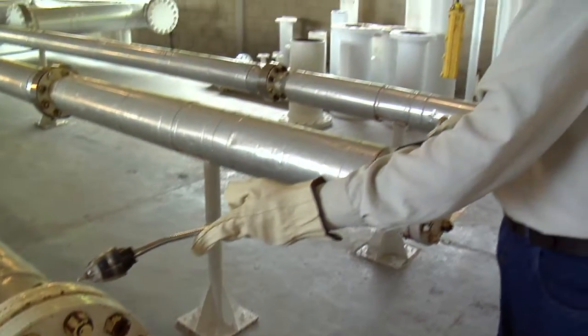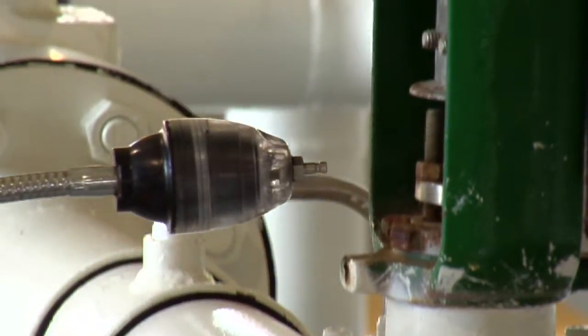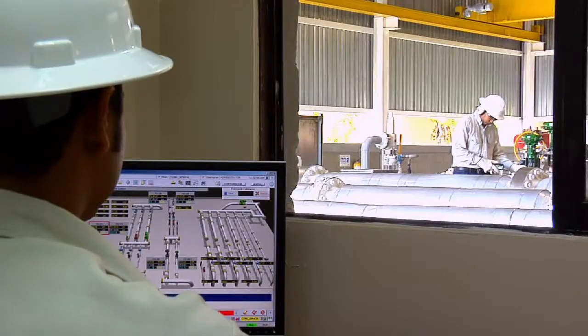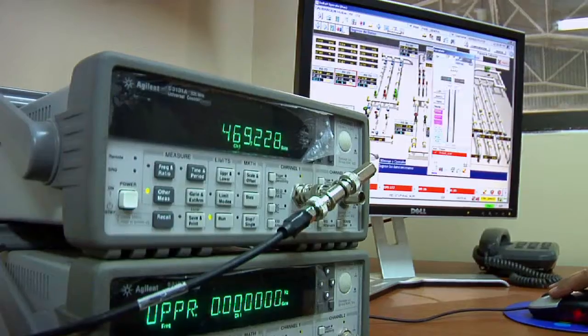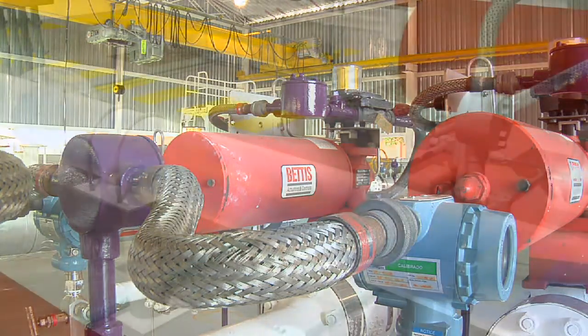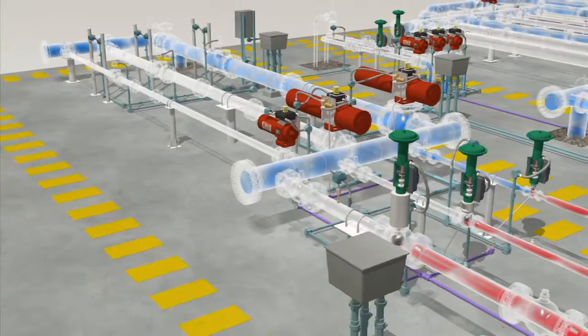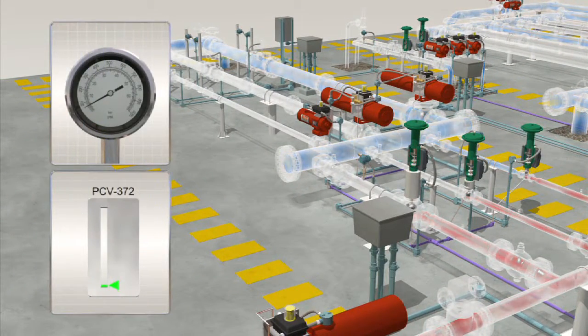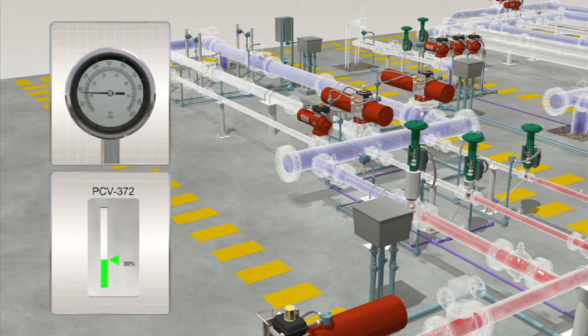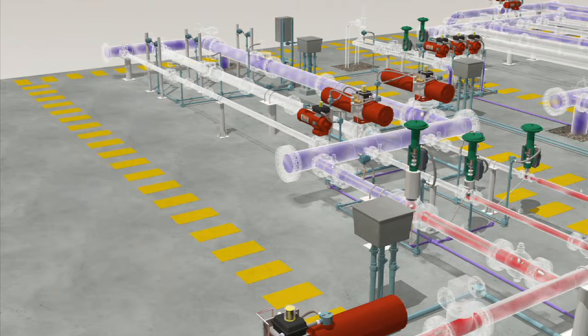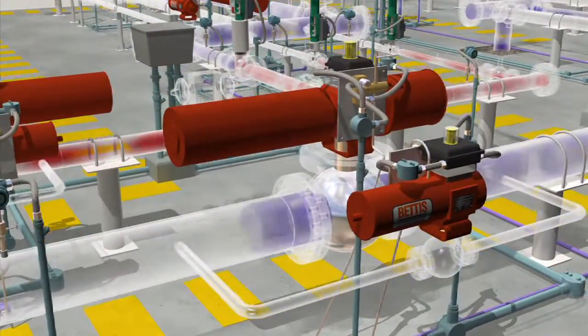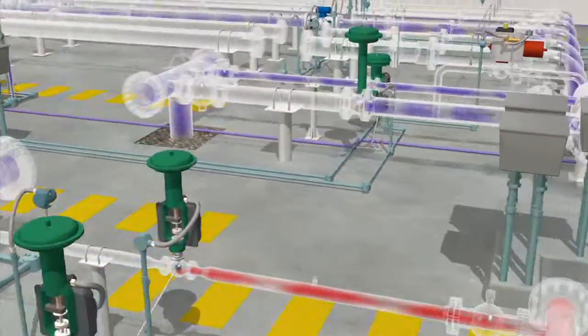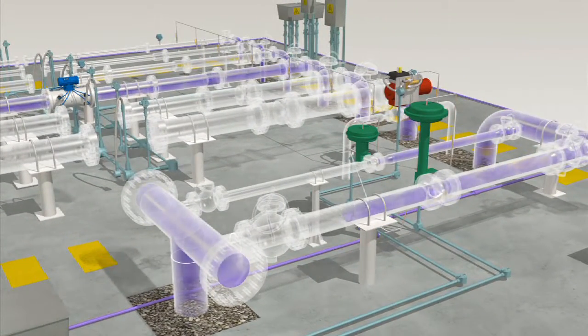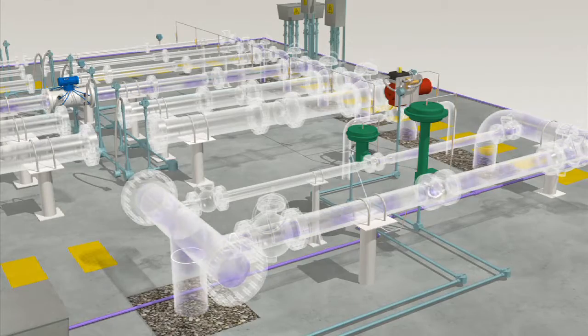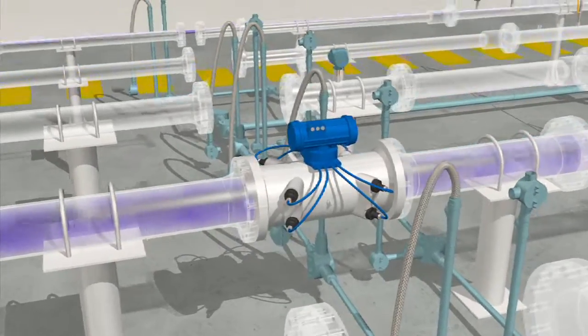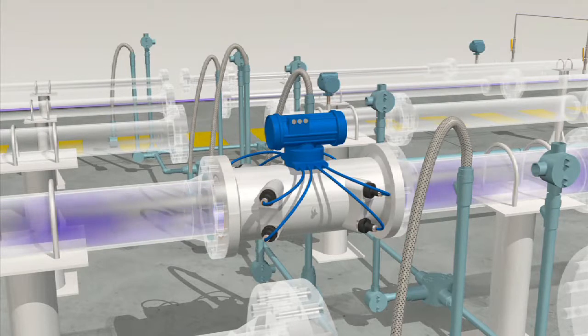With the system partially pressurized, the operator performs a leak test. When the system is proven to be hermetic, it is pressurized to the proper level for calibration. The system automatically selects the pressure regulator valve, depending on the flow and pressure required to calibrate the meter. With the required calibration pressure, the system is stabilized at the minimum flow for the selected master turbine. This allows us to protect the customer's meters and the infrastructure of our installations from possible damage caused by overspeed, and to start the process at the first calibration point without risk.